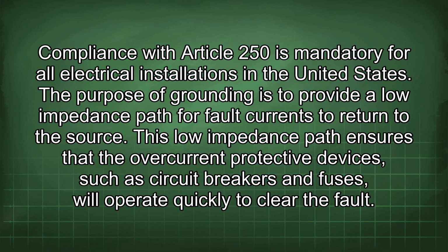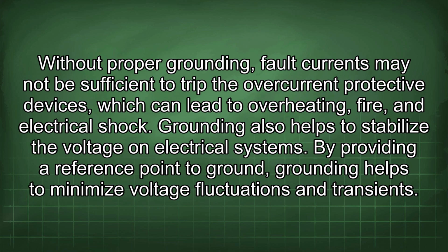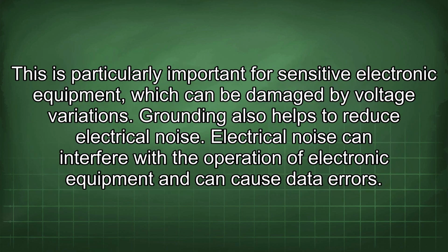This low-impedance path ensures that the overcurrent protective devices, such as circuit breakers and fuses, will operate quickly to clear the fault. Without proper grounding, fault currents may not be sufficient to trip the overcurrent protective devices, which can lead to overheating, fire, and electrical shock. Grounding also helps to stabilize the voltage on electrical systems. By providing a reference point to ground, grounding helps to minimize voltage fluctuations and transients. This is particularly important for sensitive electronic equipment, which can be damaged by voltage variations.